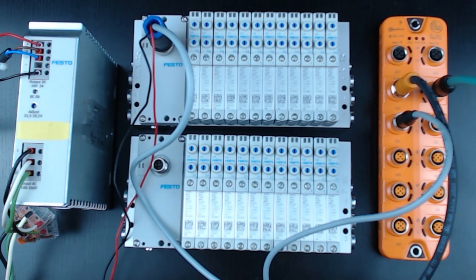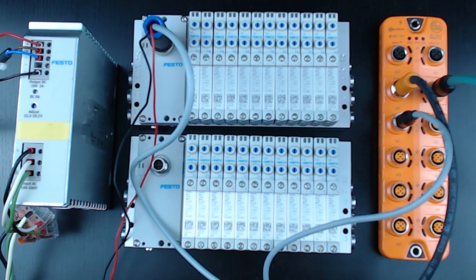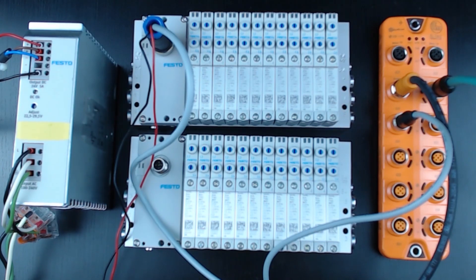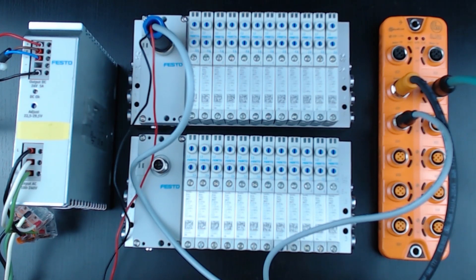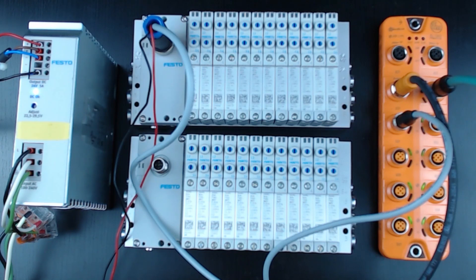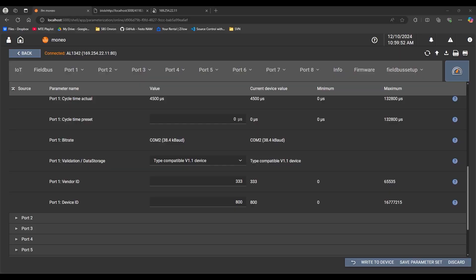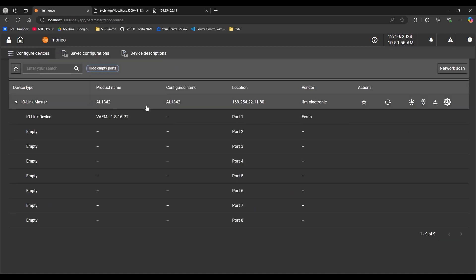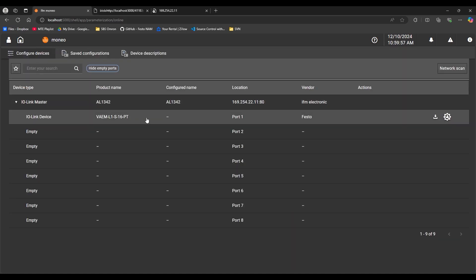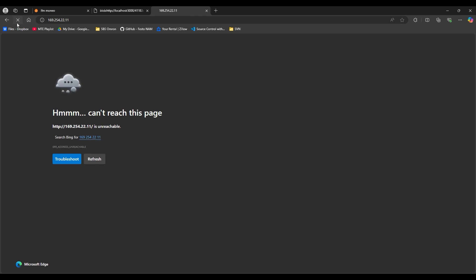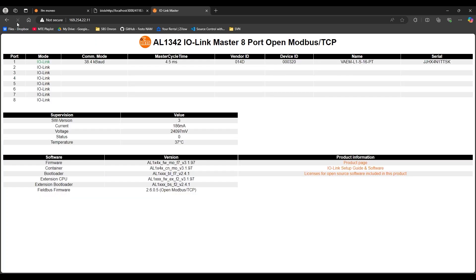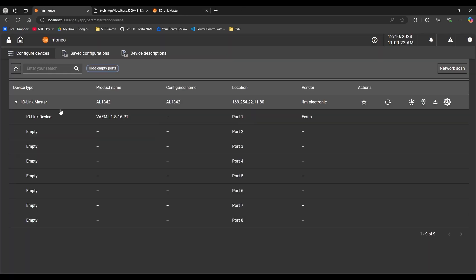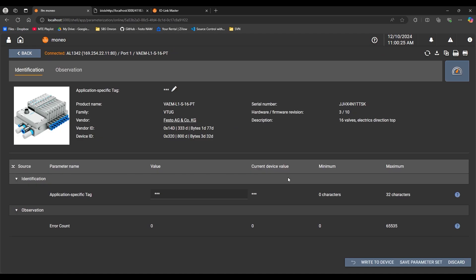Now you can see that I am connected to the upper valve terminal, I'm going to power everything back on. If I go back to Moneo, and I go back to my master here, you can still see the same device shown on port one. If I go and refresh the web server available again only through the IoT port, you can see that the same exact device, the vendor ID, device ID, and name is showing up here on port one. Notice the serial number has changed to this different value than what was shown earlier.